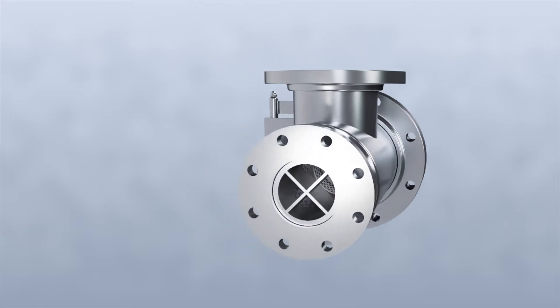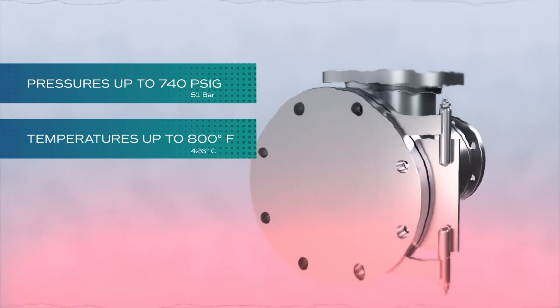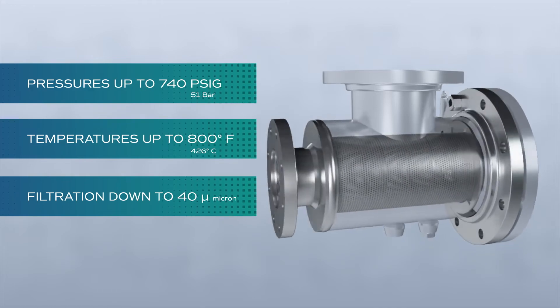Fabricated SSI Suction Diffusers can be equipped to handle pressures up to 740 PSIG and temperatures up to 800 degrees Fahrenheit, while offering filtration down to 40 microns.